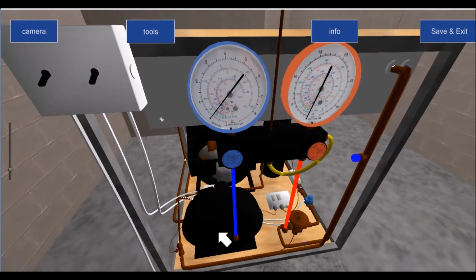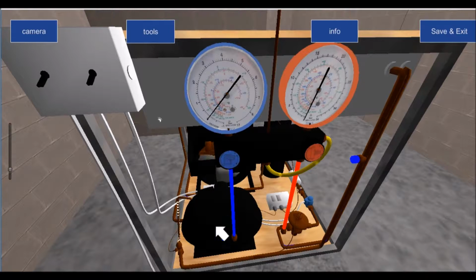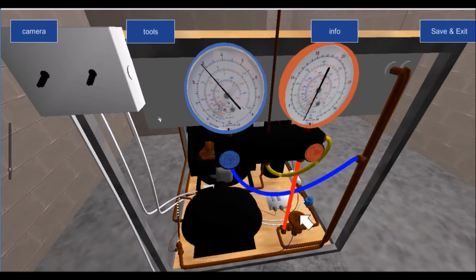This is dangling in the air, so therefore it's reading 1 bar atmospheric pressure, which is the equivalent to 0 gauge pressure. So again, remember, absolute pressure at sea level is 1.013 bar or something like that. But what we have here is a reading of 0. So gauge pressure is always going to be 1 bar less than absolute pressure. But as soon as I connect my hose line on, I get a pressure reading straight away. Now I haven't done anything with these valves. So that brings me back to what I was trying to show you a little bit earlier.